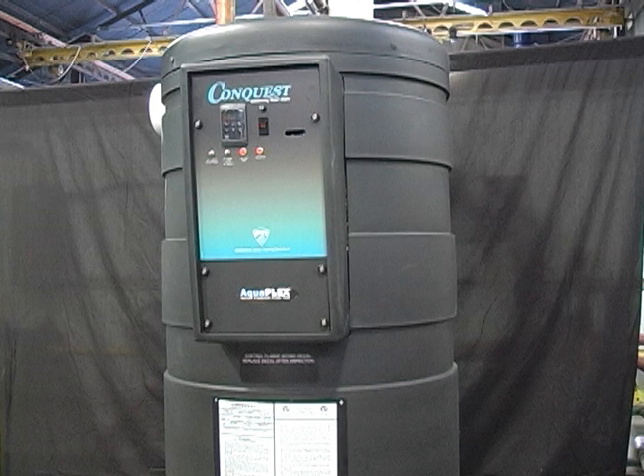Before attempting to start the water heater, the flame safeguard circuit must be verified. This is done by attempting to start the water heater with no gas flow, which should cause the water heater to fail to light and to then lock out.